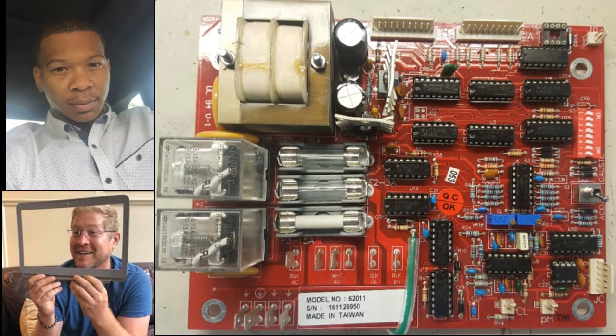Okay. Now, as far as the voltage, that would be a thing with the voltage regulator. It's right next to the capacitors. And you have a positive 12 and negative 12. Now, if they get to about 11.8 volts, then the board starts to heat up, in particular on the voltage regulator. And when voltage drops, the amperage increases. But once that amperage increases, it causes the relay to chatter back and forth, and to a certain extent it actually melts together and even melts the relay socket as well.